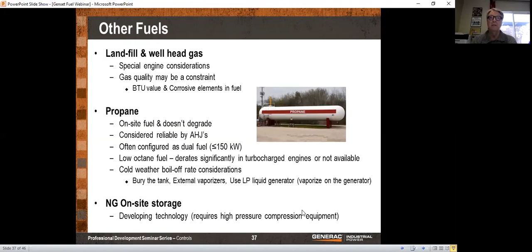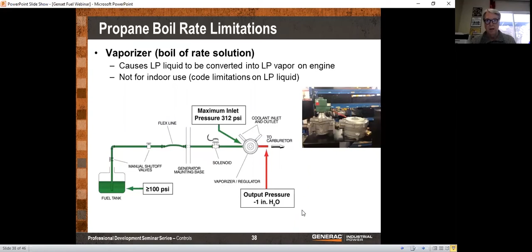Now, one of the issues with propane is you have to vaporize. It's in the tank, and this would be with LNG as well, in a liquid state, and so you have to get that to vaporize in order to use it in the generator. And if it's an underground tank, no problem. If it's an above ground tank and it gets very, very cold, then you may have a problem with vaporization. And in that case, it's a pretty simple situation where we just pipe the liquid to the generator rather than the gas, and we put a vaporizer in the generator that vaporizes it there. Not a problem. You just have to realize that you have to do it.